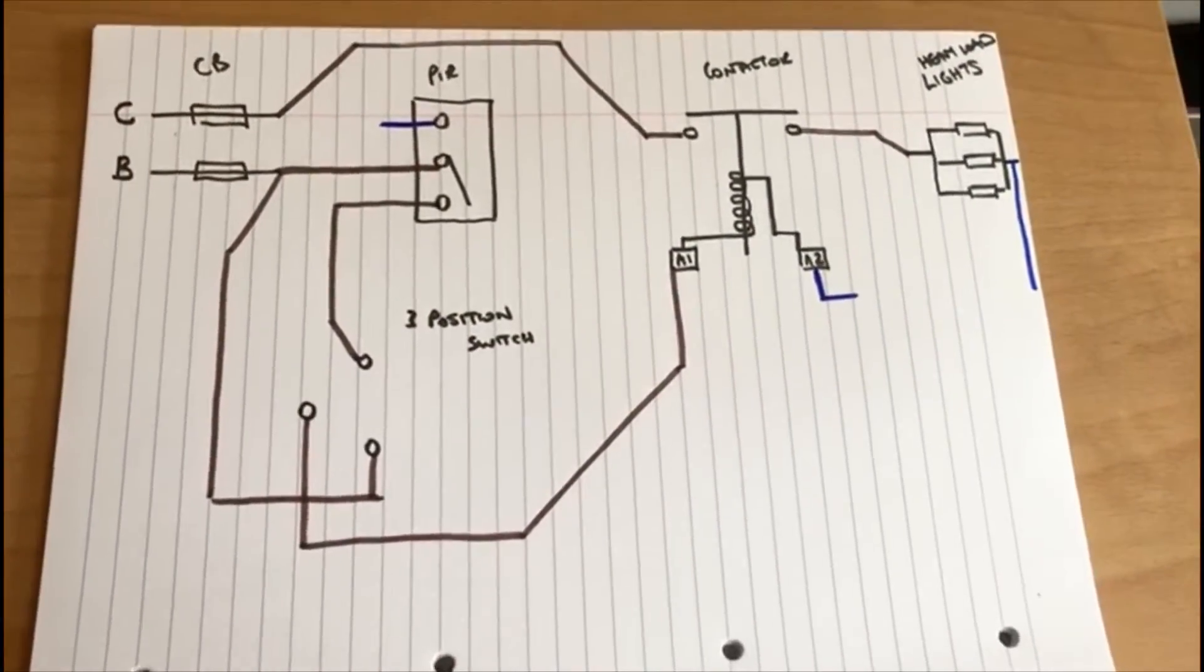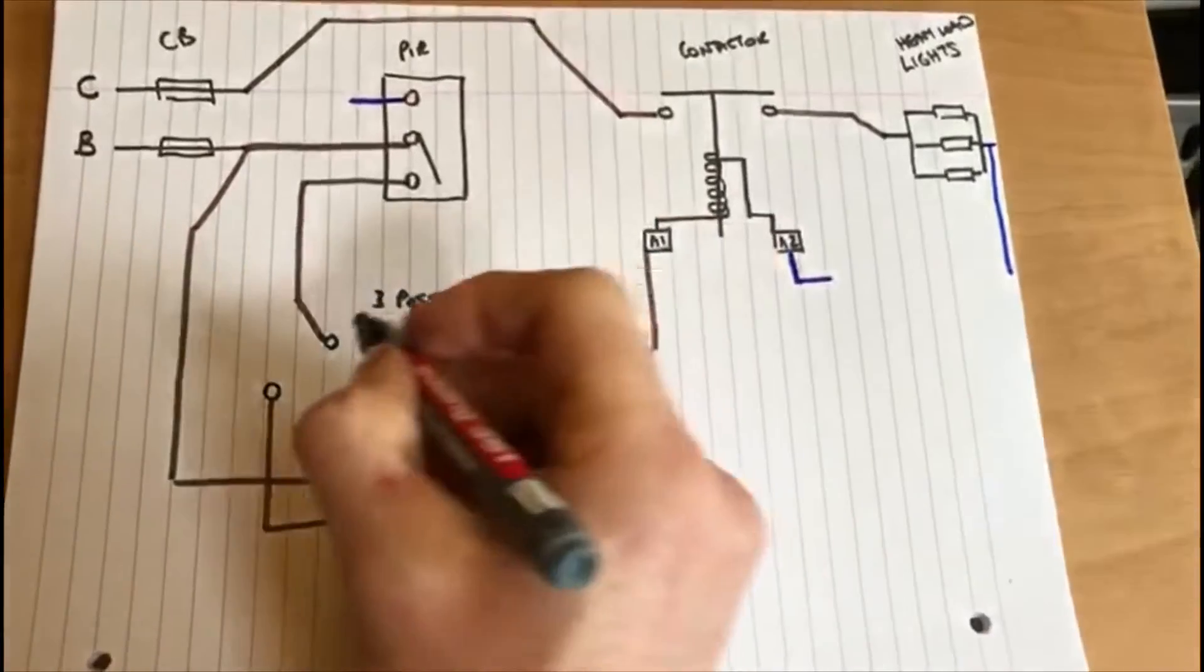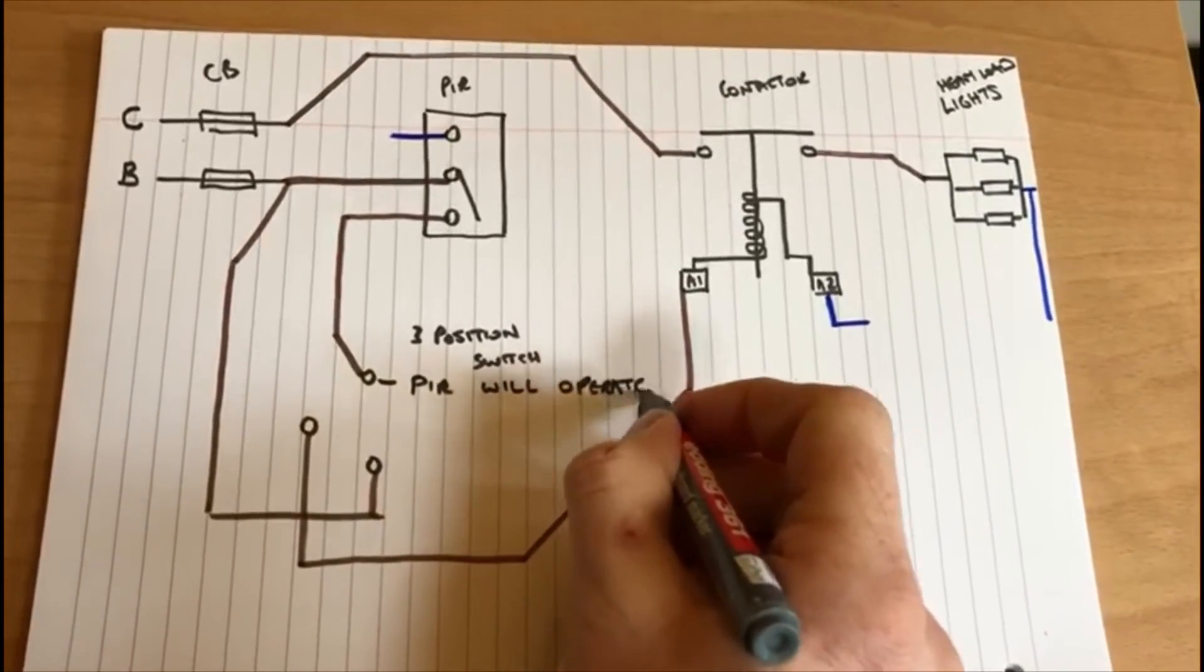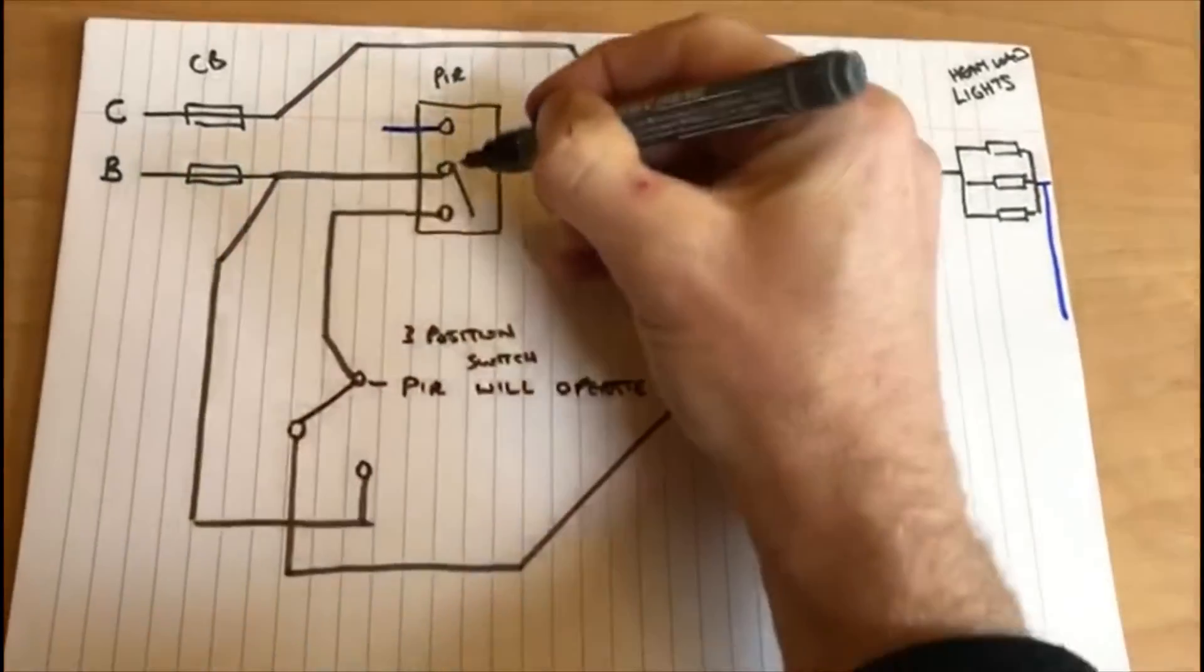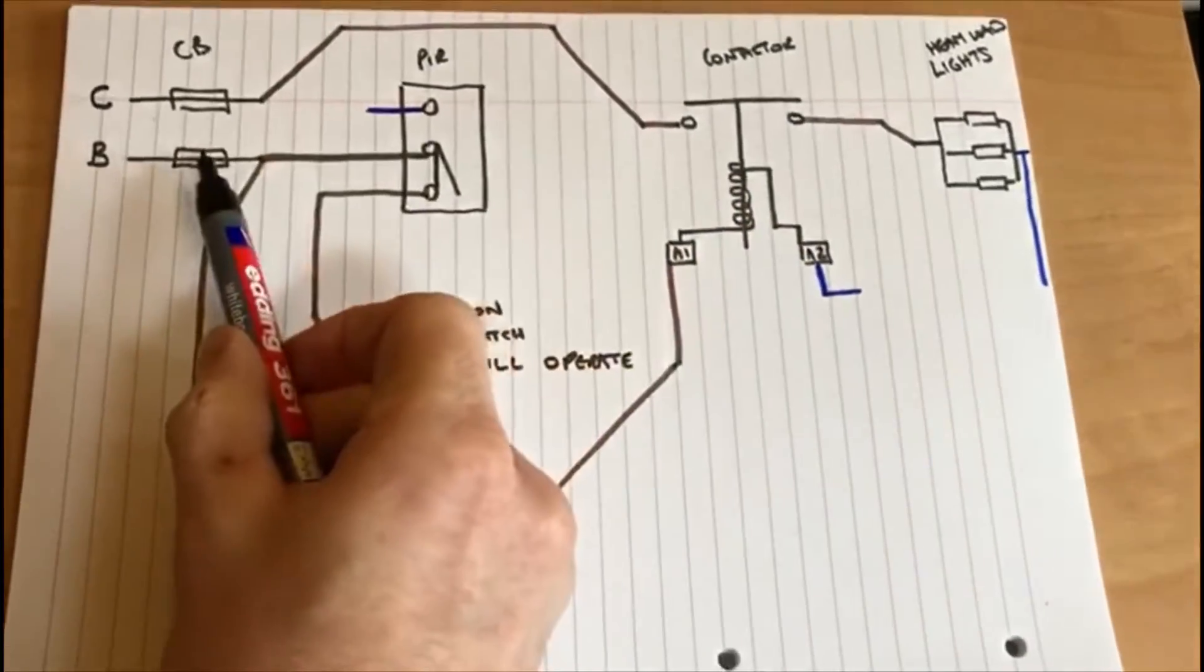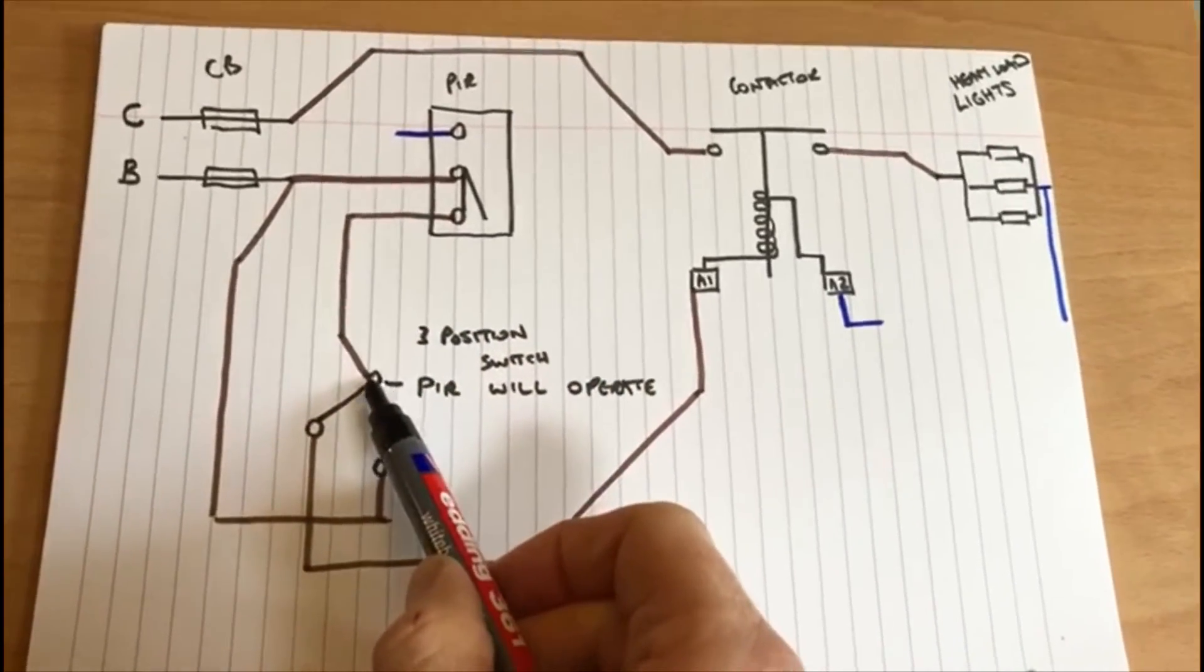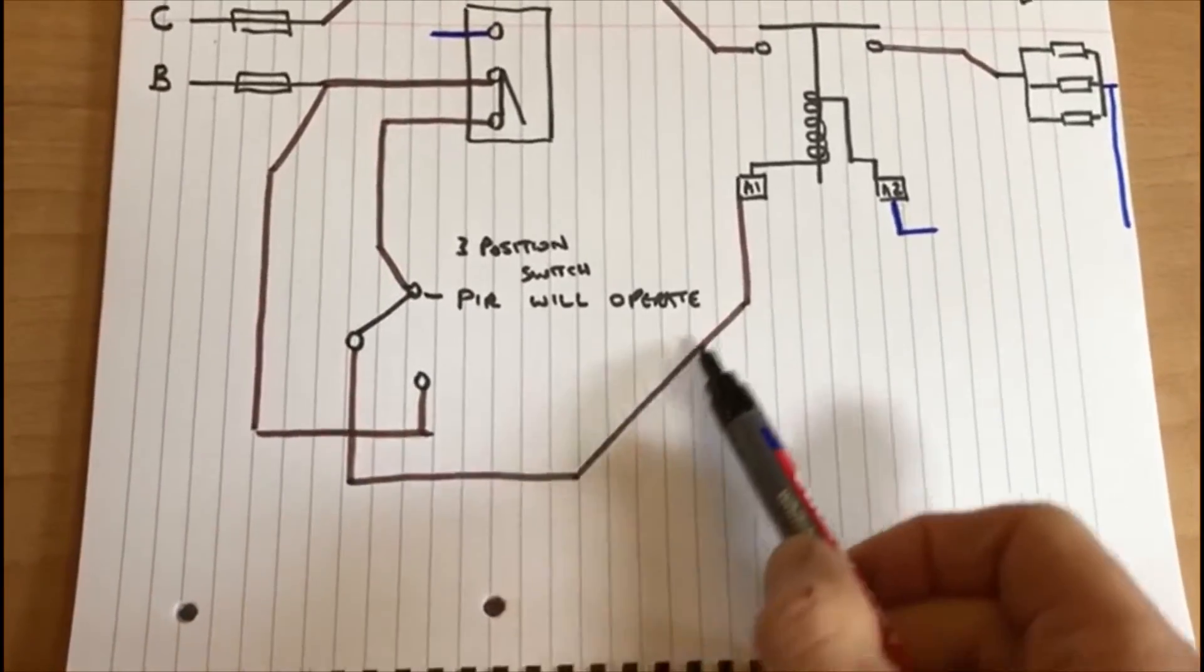Let's just look at the configuration now. So in this position the PIR will operate. So if it was in that position there and the PIR operates and closes, picks someone up walking through, now the electricity is going through here, through to here, through to here, back through the switch, back all the way across to the coil.